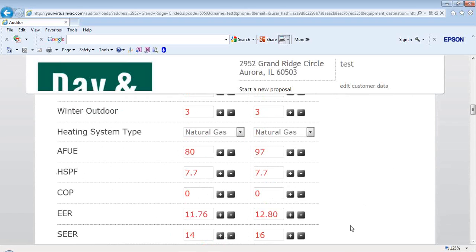However, on the heating side, the AFUE number does not take into account the motor efficiency. So for heating and for general recirc, it's not being captured yet in this current tool, and we're working on getting that changed. For cooling and SEER, it is already built into that SEER number. That's a great question, Larry. In fact, I'll make a note to follow up and see what the status is of getting the motor efficiency adjusted in this tool.